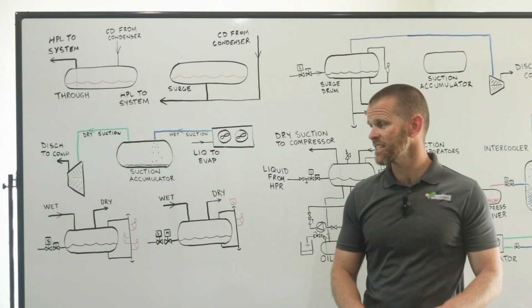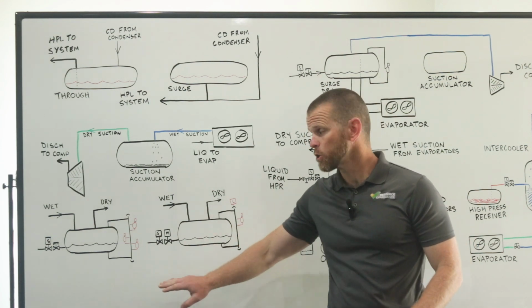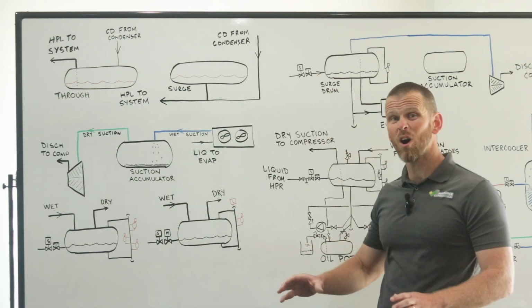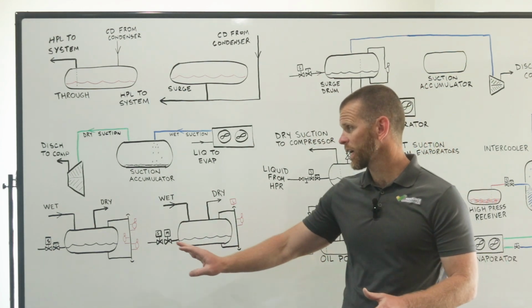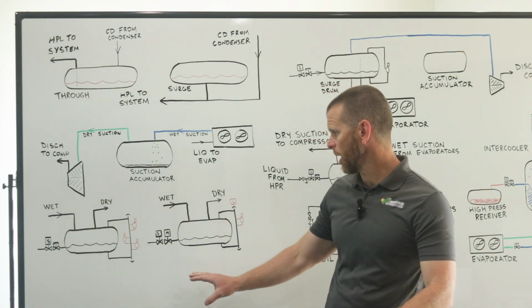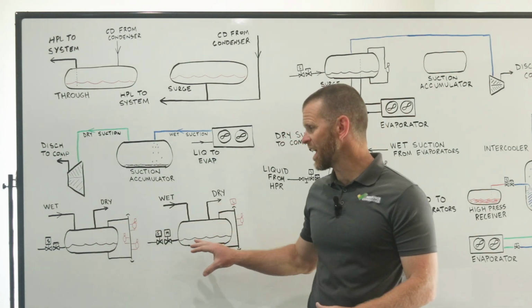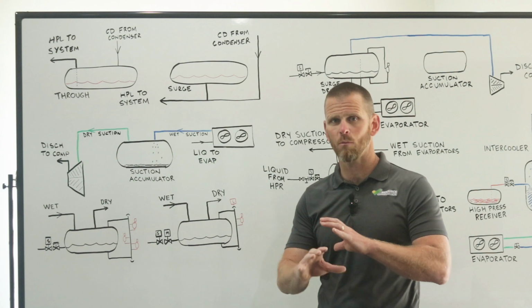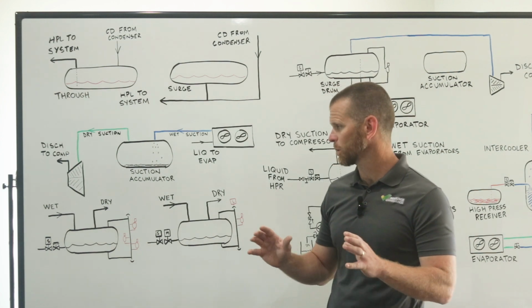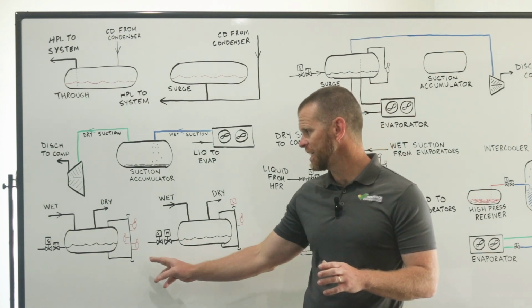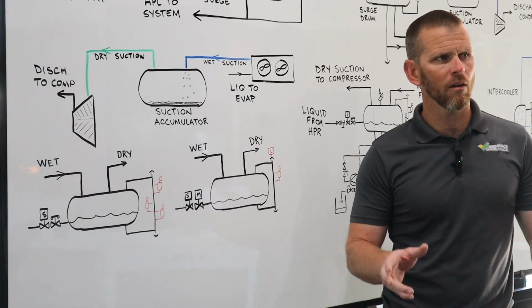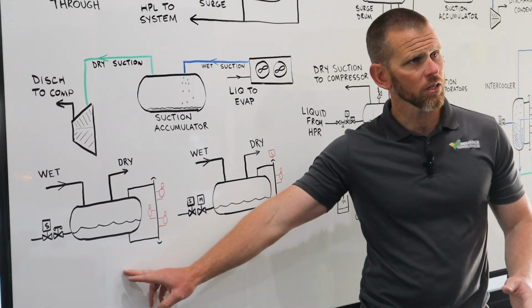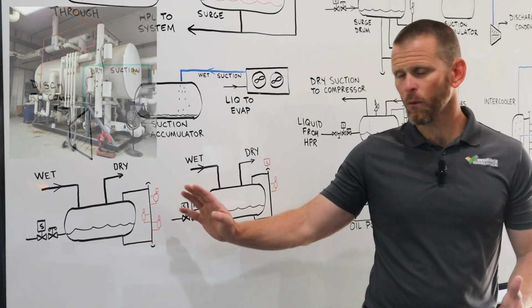Let's contrast a float tree setup to a level probe setup on a recirculator. All right, so we're looking at two recirculators here. I haven't shown the pumps, you can imagine those, but we've got two vessels. They're pretty much configured the same. We'll say they're the same size, diameter, length, but the primary difference is in the method of level control. In the first here on the left, we have what I'm calling a float tree.